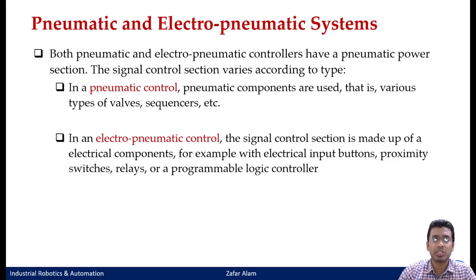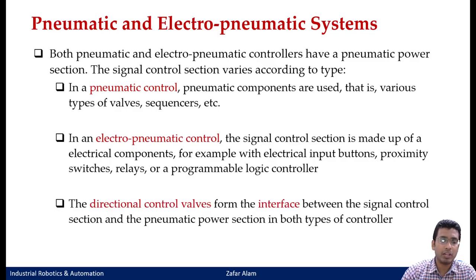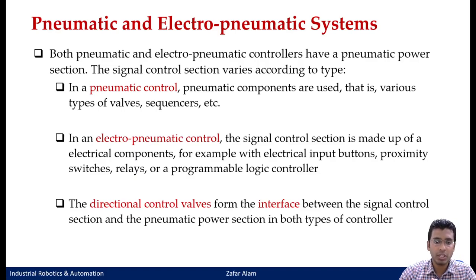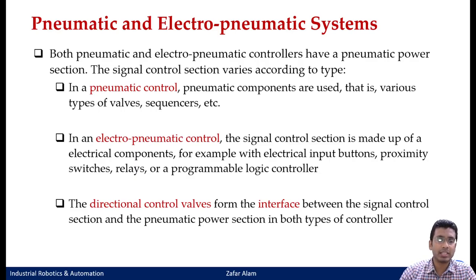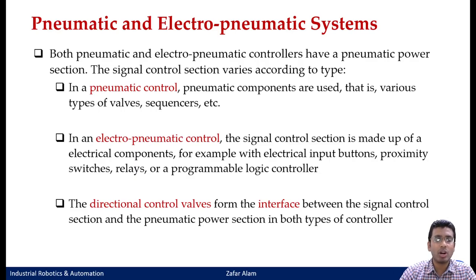In electro-pneumatic control, all signals will be electrical, and they are finally processed either using relays or PLCs, which we will study in the next module. The signal output will again be a 5/2 valve, but it will be a solenoid operated valve instead of a double pilot operated valve. Your direction control valves form an interface between the signal control section and the power section.